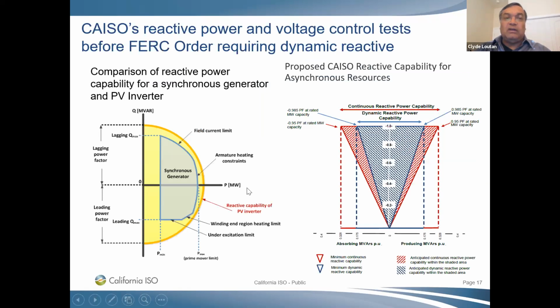So moving on to the voltage control test. I did not want to change this plot on the right because this is what we wanted to test the unit at. Back then, FERC did not come up with a voltage requirement for inverter-based resources. So in the 2017, early 2018 timeframe, at the California ISO, we were contemplating reactive support, and at the very top, at full megawatt output, we wanted to see 0.95 lead, 0.95 lag in terms of reactive or voltage control at the very maximum megawatt output. And the V shape really tells you that as the megawatt output decreased, it was okay to decrease the reactive support. And even below 10% of the actual megawatt output, we were not expecting these plants to respond.